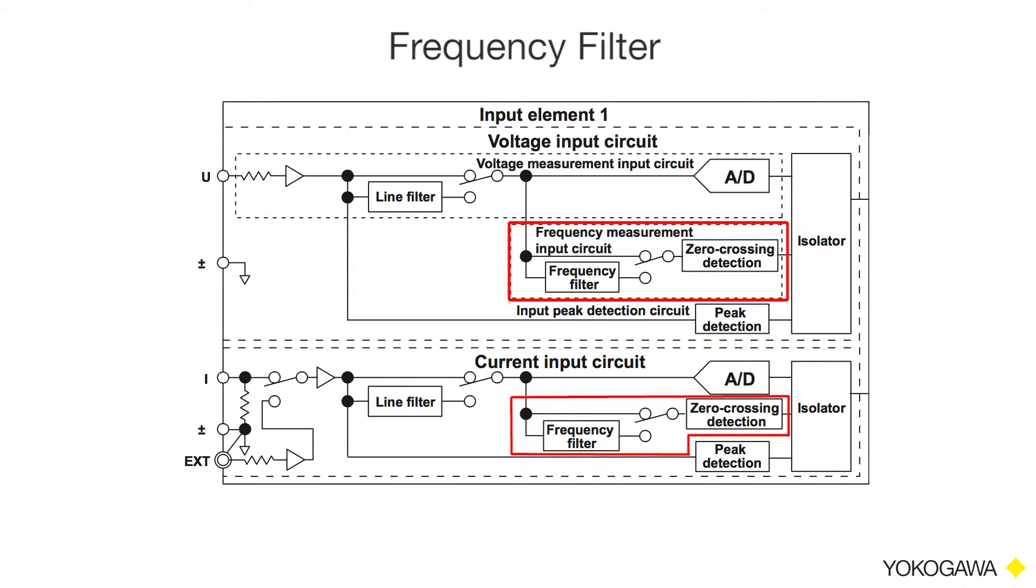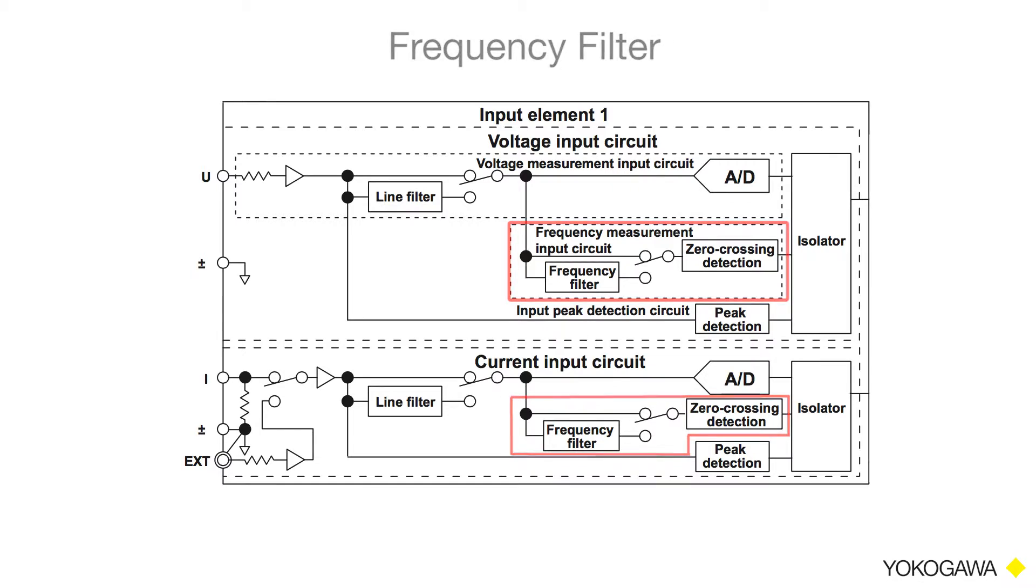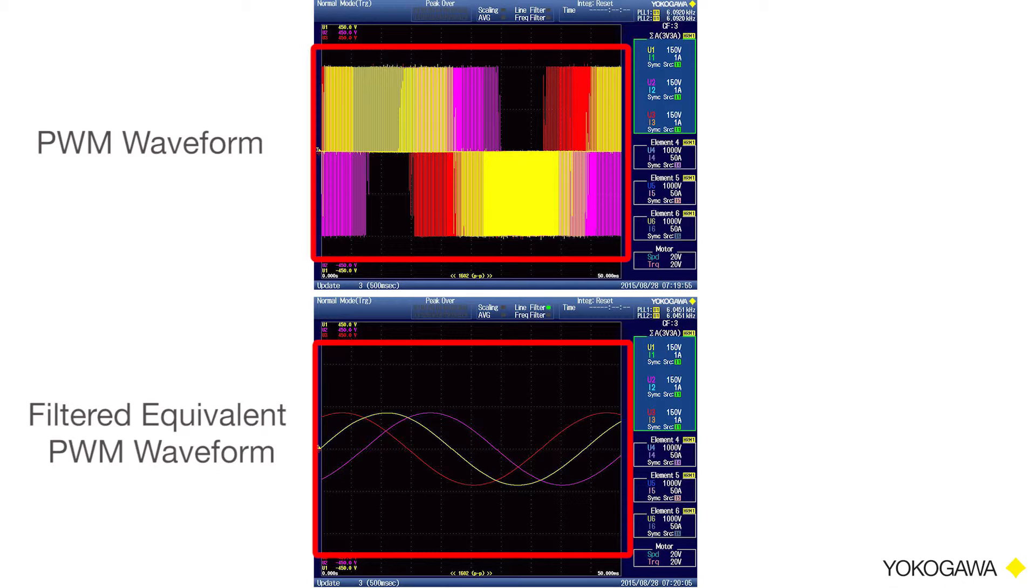A typical use of this filter comes in handy when measuring PWM signals. Since PWM signals have a fundamental frequency with high switching frequency components like this, power analyzers can sometimes struggle with locking onto the measurement period of the signal's fundamental frequency to make accurate power measurements.